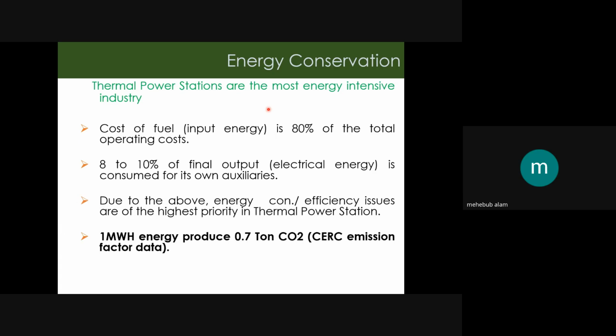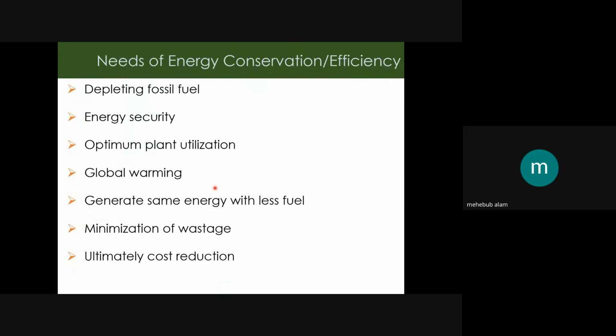Now, if we see the cost, fuel is 80% of the total cost of any thermal power plant, and 8 to 10% of the energy is consumed as auxiliary power consumption. Due to this, energy efficiency and energy conservation is a very crucial factor, because 8 to 10% of the produced energy is consumed by its own auxiliaries. The need is also there because, day by day, we know that the fossil fuel source is limited and will be depleted, and there is an energy security issue, optimum plant utilization, the global effect, the minimization of wastage, and ultimately cost reduction.